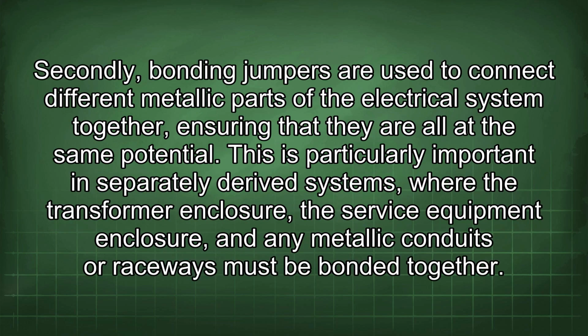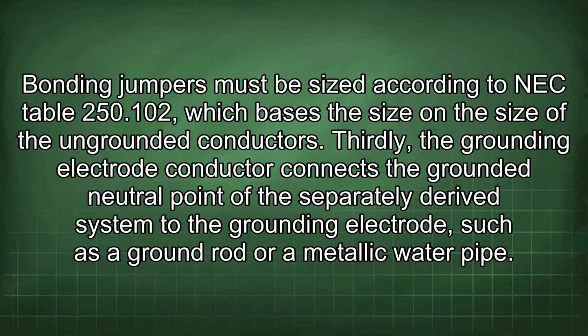Secondly, bonding jumpers are used to connect different metallic parts of the electrical system together, ensuring that they are all at the same potential. This is particularly important in separately derived systems where the transformer enclosure, the service equipment enclosure, and any metallic conduits or raceways must be bonded together. Bonding jumpers must be sized according to NEC Table 250.102, which bases the size on the size of the ungrounded conductors.